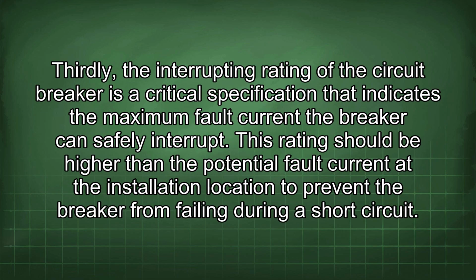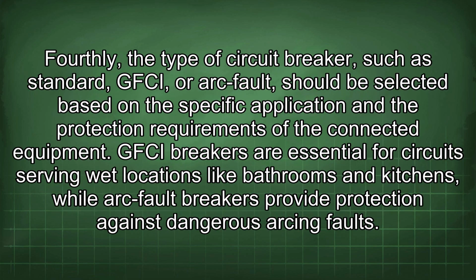Thirdly, the interrupting rating of the circuit breaker is a critical specification that indicates the maximum fault current the breaker can safely interrupt. This rating should be higher than the potential fault current at the installation location to prevent the breaker from failing during a short circuit. Fourthly, the type of circuit breaker, such as standard, GFCI, or arc fault, should be selected based on the specific application and the protection requirements of the connected equipment.